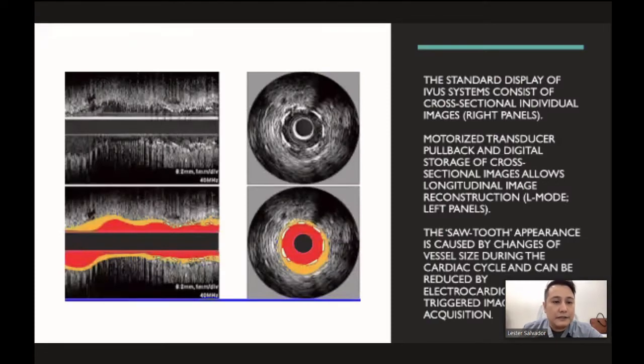So this is the standard display of an IVUS system, which consists of cross-sectional individual images on the right, and the motorized transducer pullback and digital storage of cross-sectional images allow a longitudinal image on the left. The sawtooth pattern that you see here is caused by the change in vessel size during the cardiac cycle and can be reduced by electrocardiogram-triggered image acquisition.